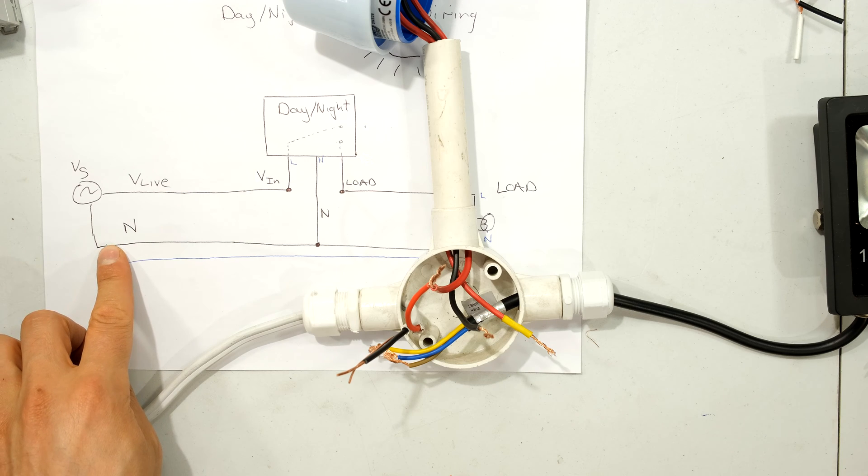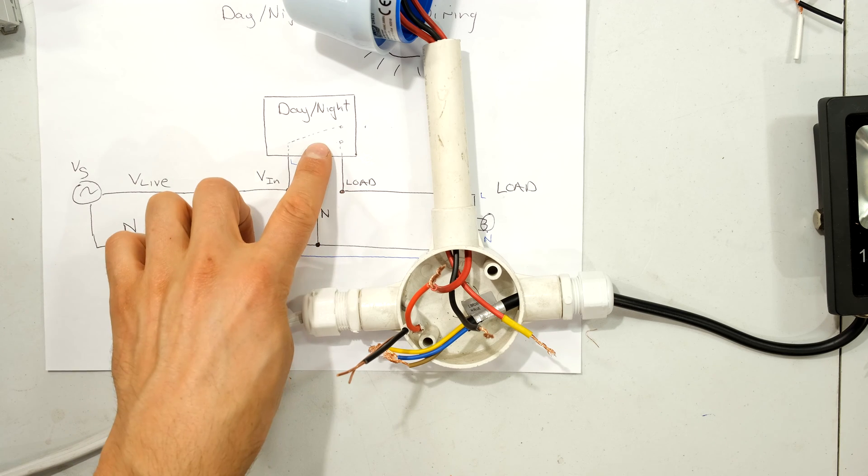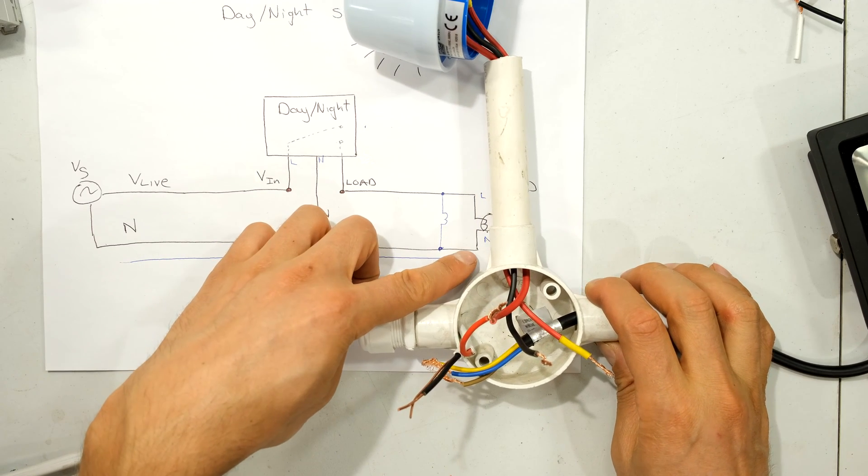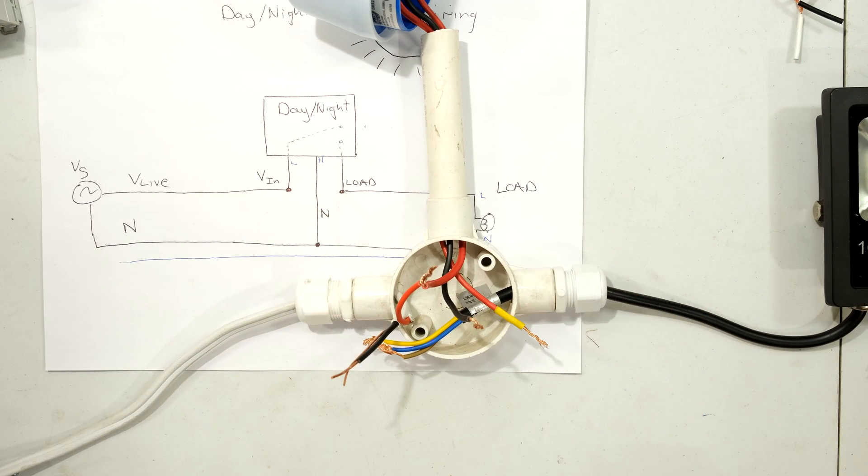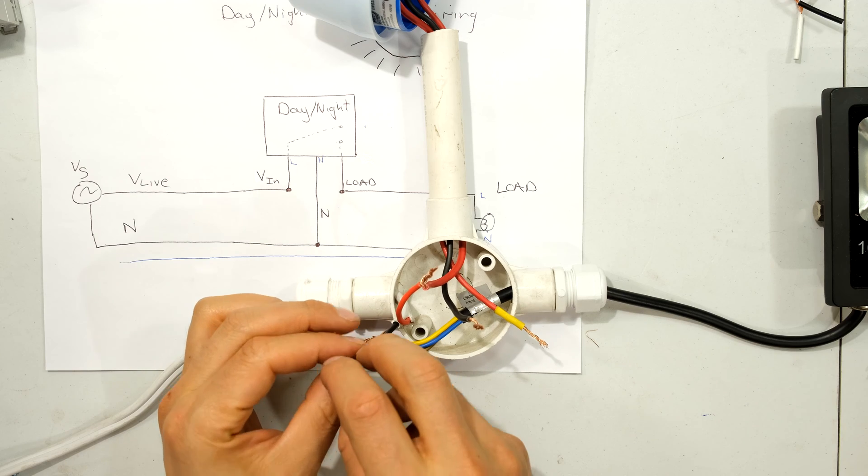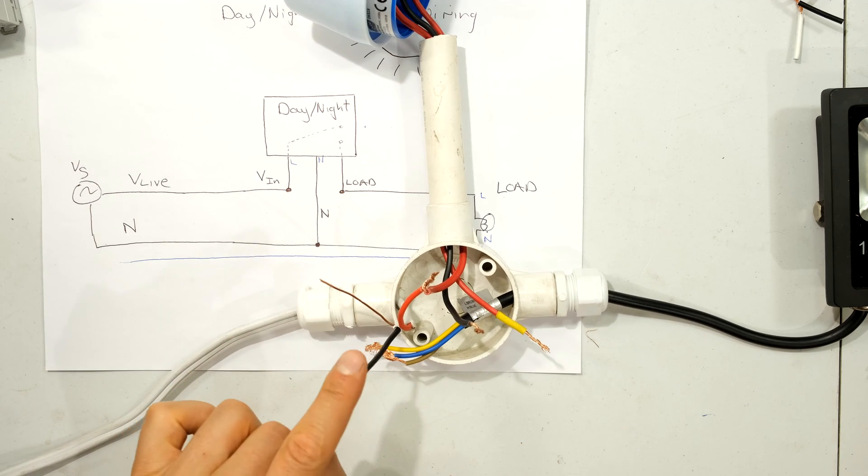Right, now the neutral from the supply goes to the day-night switch and also feeds the load, my light. So that means I'm going to have three wires joined together. So the neutral from my supply is this black wire over here.